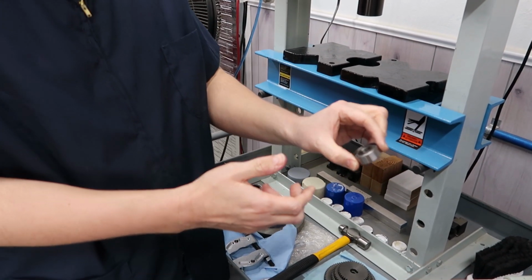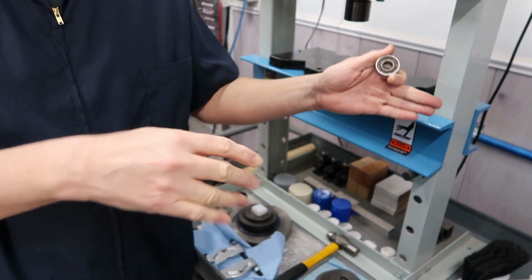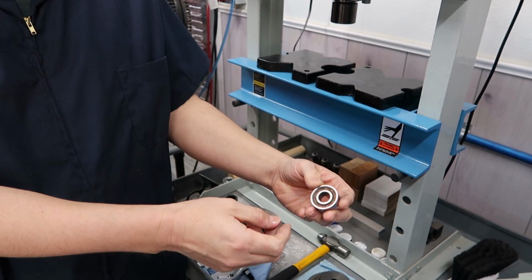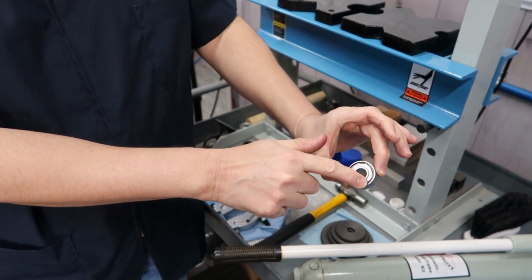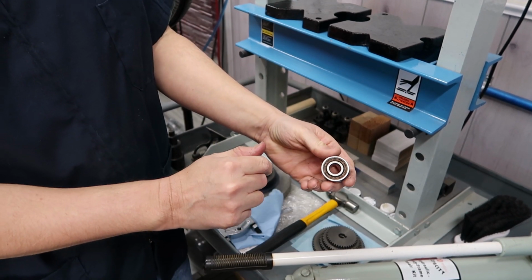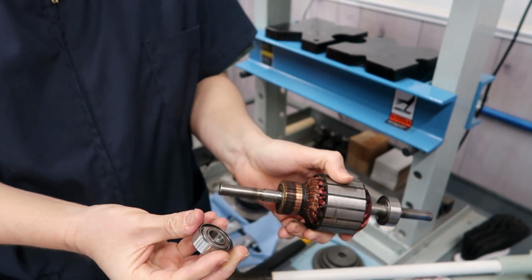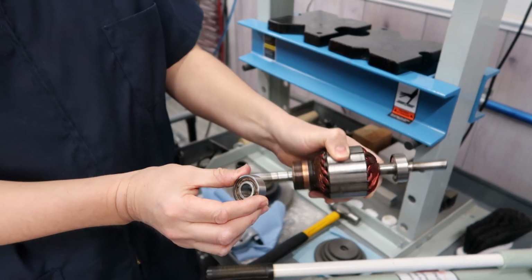Yeah, you know what? When I ordered the bearings, I removed the caps off both sides of the motor so I could get the size and the part number of the bearings. I just saw the open face, and I thought, okay, they're open bearings. But when I took the motor apart, as you probably noticed on the disassembly, it does have a shield on one side, and it's open on the other. So they installed the bearings with the shields on the inside. If we look at the existing one that's still installed, it has a shield. Both shields are facing inside, and it's open on the outside. Oh, okay. Thanks.